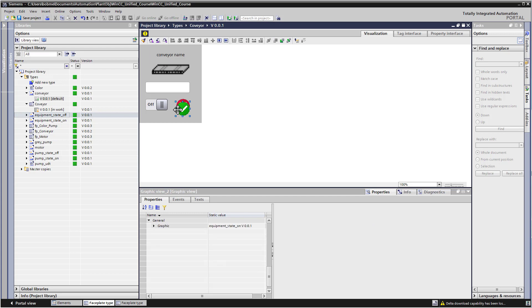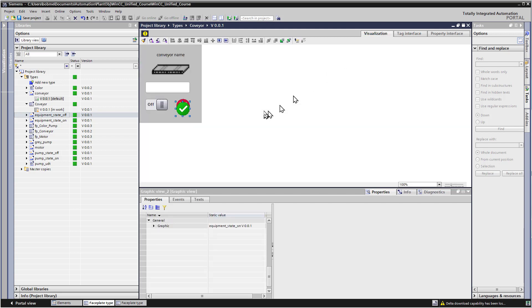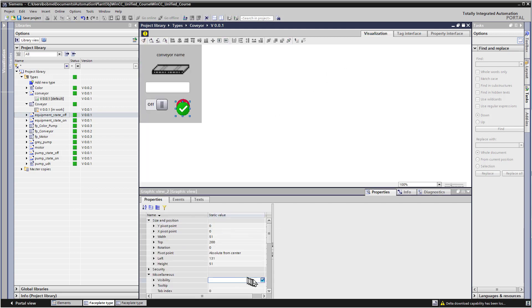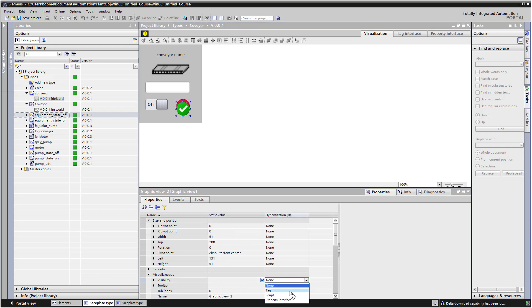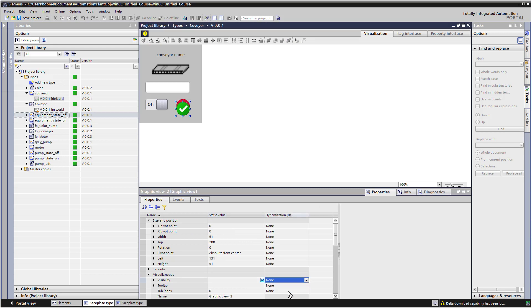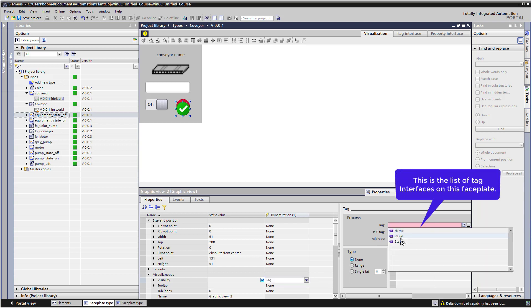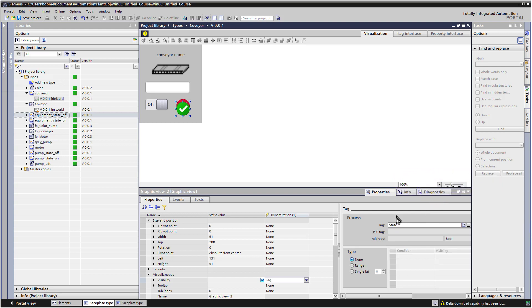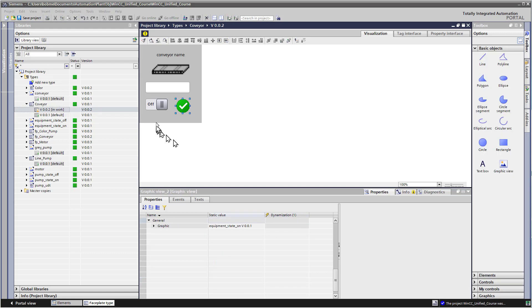We only want to show this if our state is 1. If it's 0, we don't want to show it. So we could come here and go to our properties and go to visibility. And then just set this to a tag. If I click this, it's only going to show whatever we've set up here. I kind of think of these as internal faceplate tags. But if we just set up to tag state, if it's true, then visible is going to be true, and you're going to see it. If it's false, then you're not. And you're going to see the X behind it.